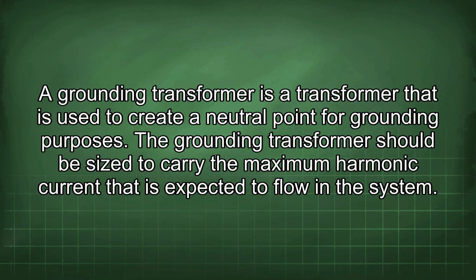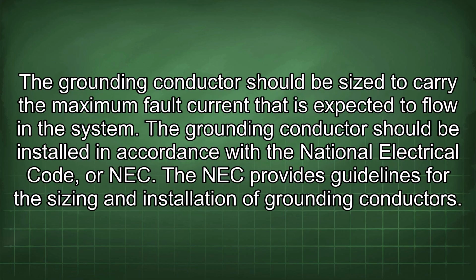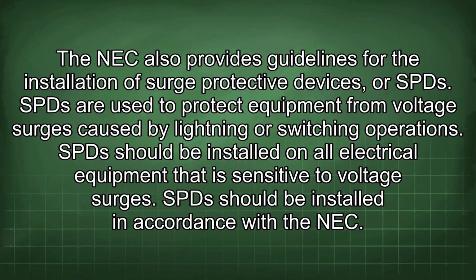The grounding transformer should be sized to carry the maximum harmonic current that is expected to flow in the system. The grounding conductor should be sized to carry the maximum fault current that is expected to flow in the system. The grounding conductor should be installed in accordance with the National Electrical Code, or NEC. The NEC provides guidelines for the sizing and installation of grounding conductors. The NEC also provides guidelines for the installation of surge protective devices, or SPDs. SPDs are used to protect equipment from voltage surges caused by lightning or switching operations.